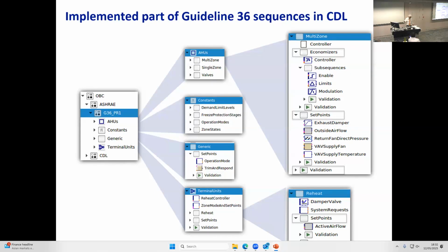That's what happens, as illustrated - don't try to read the details too much. This particular case study involved secondary HVAC systems, in this case multi-zone VAV together with an air handling unit. That's where a lot of the work in building a control system and control sequences of operations for a commercial building happens, because if you have multiple air handlers and many zones in the building, you really want to automate this process as much as you can.